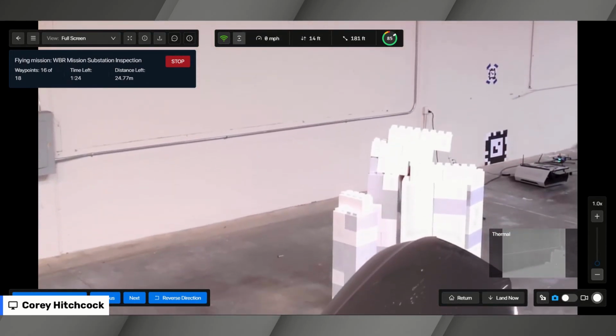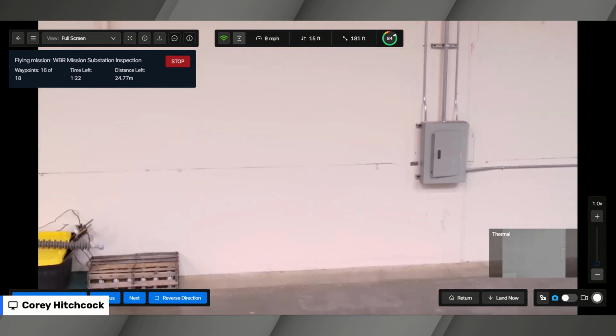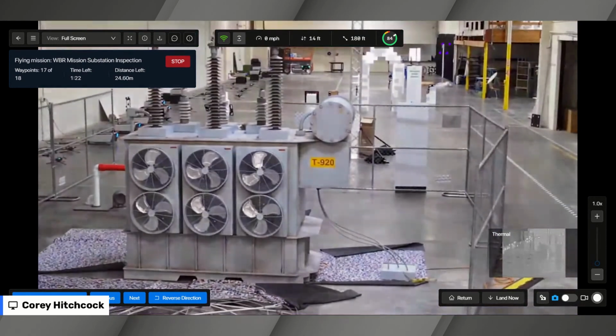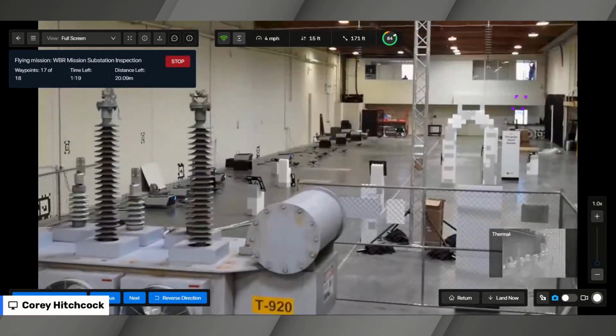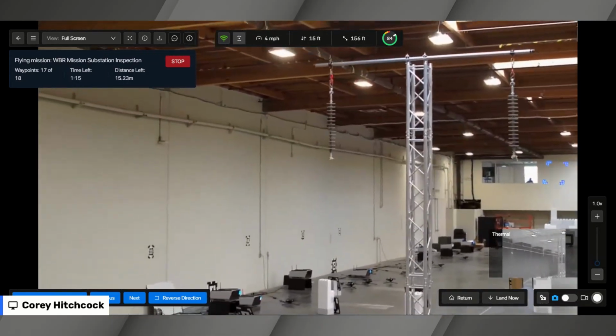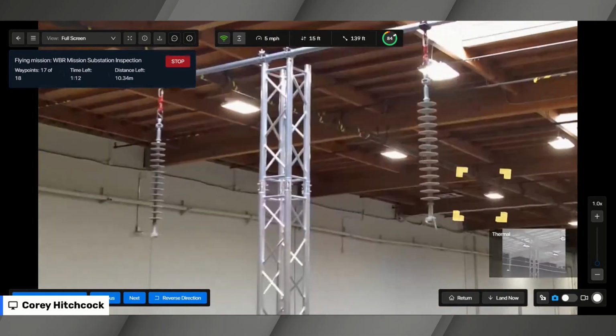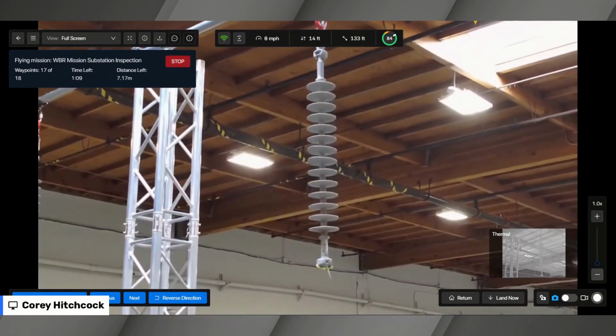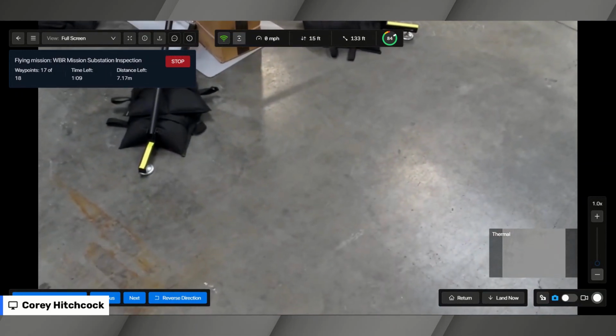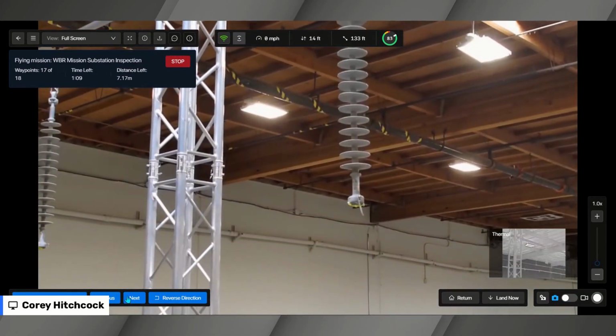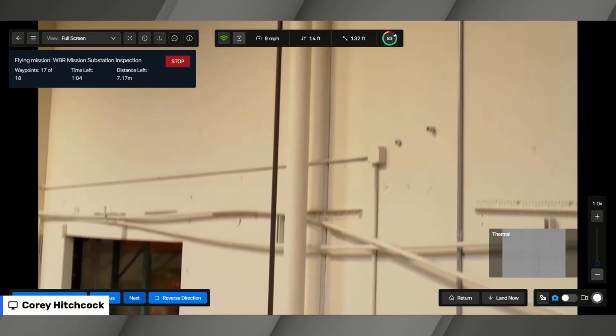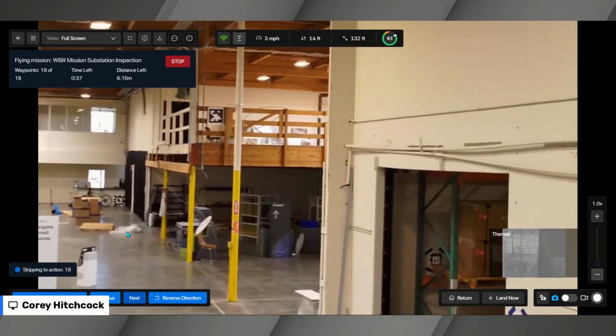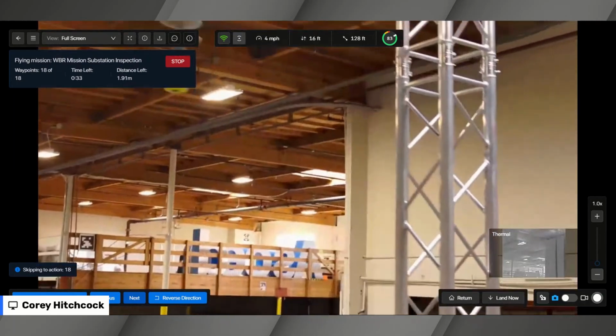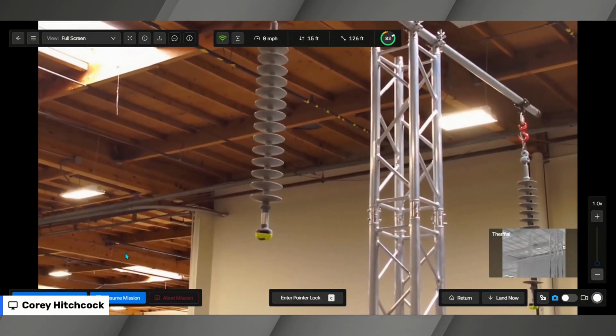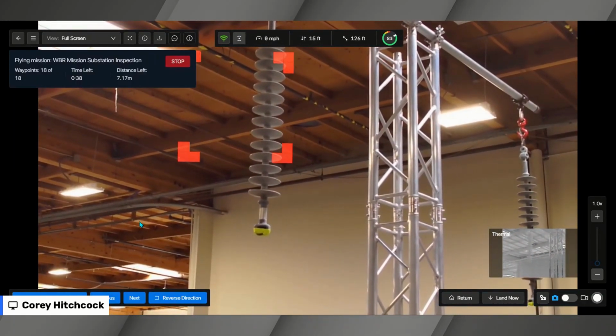Having that drone to be able to dispatch to that event-based patrol, to the section of line that the distribution automation scheme has identified the fault, that's something that I think is super valuable and could revolutionize the way distribution outages are handled, because you limit your CMI by being able to re-energize the circuit without having your lone worker have to drive three hours to get to that spot and then patrol that line.